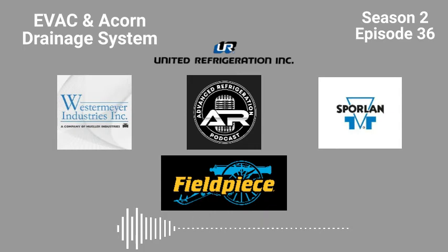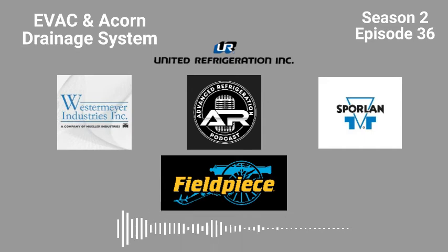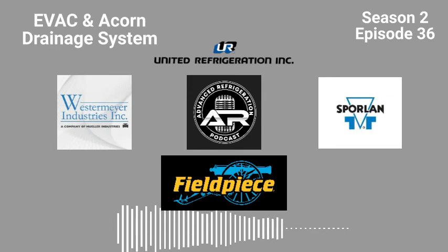Really? Also, if you guys aren't aware, remember how we said the pumps are water piloted driven pumps where they have to have water going through them. They actually have to maintain a water level inside of them at all times. I believe it's supposed to be between a half and three quarter full. There's almost a fuel gauge on top of the pump that says E and F for full, and that water level has to be maintained. There's a float inside the back end of this pump assembly that maintains a certain level. So you can have not enough water and you can also have too much water. Like Kevin said, they're not supposed to take on full bore water, but they still need the water to operate.